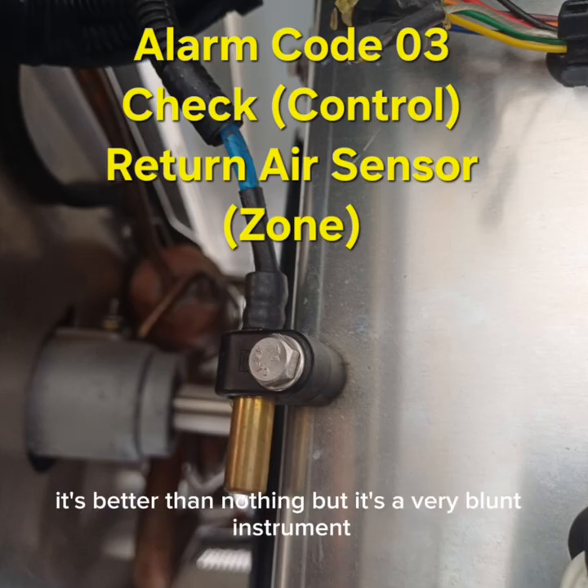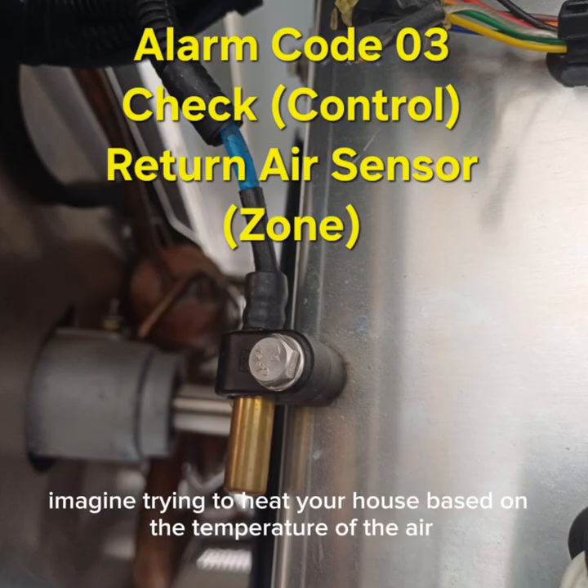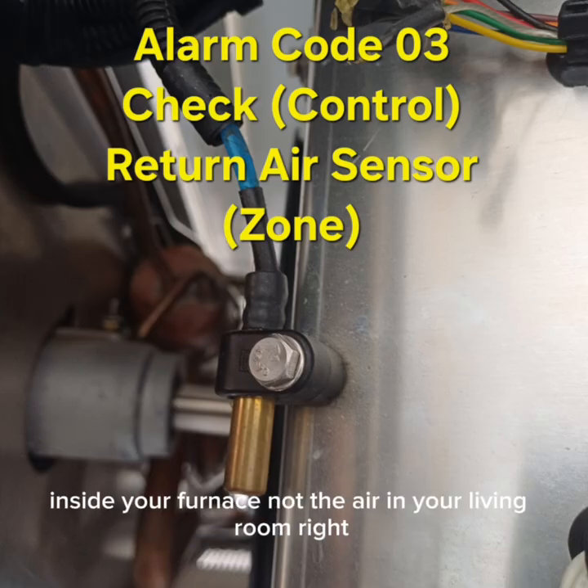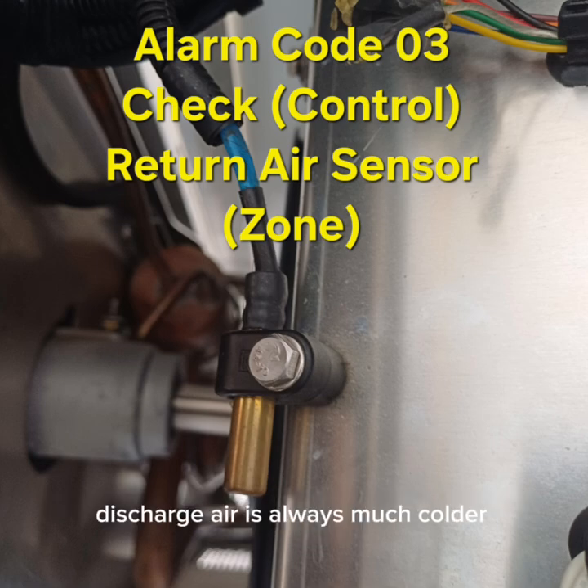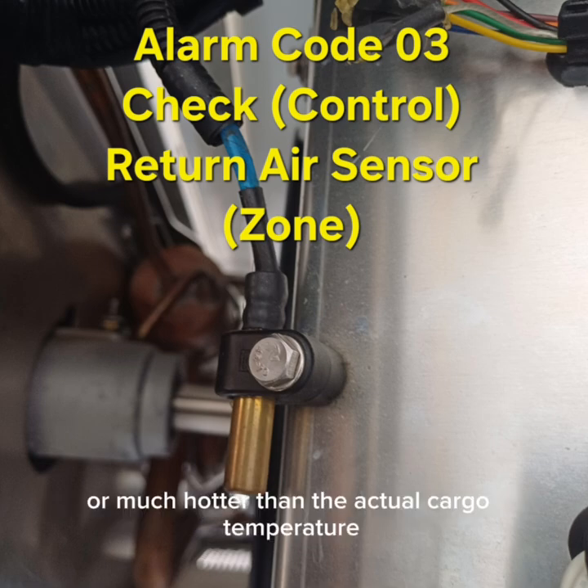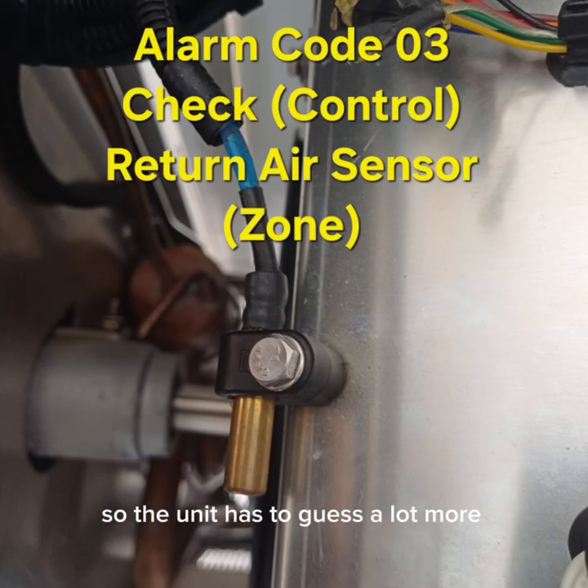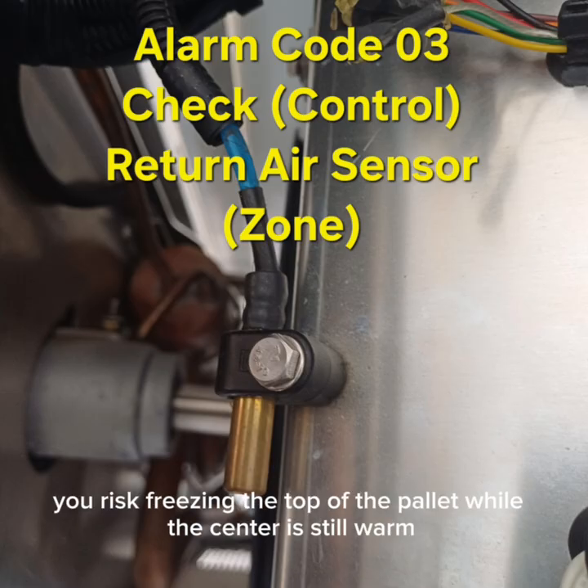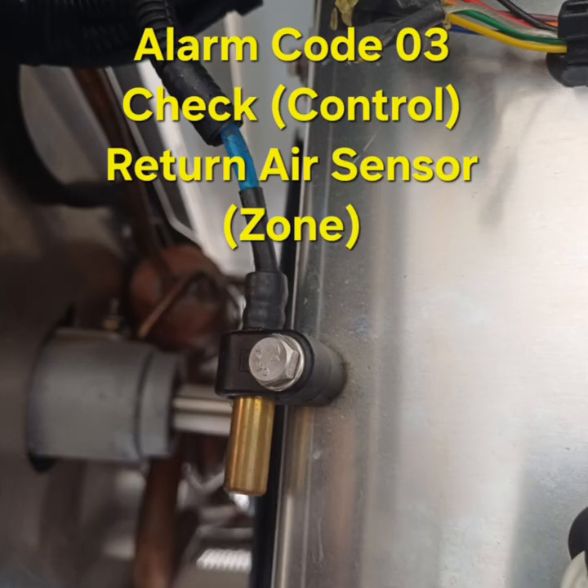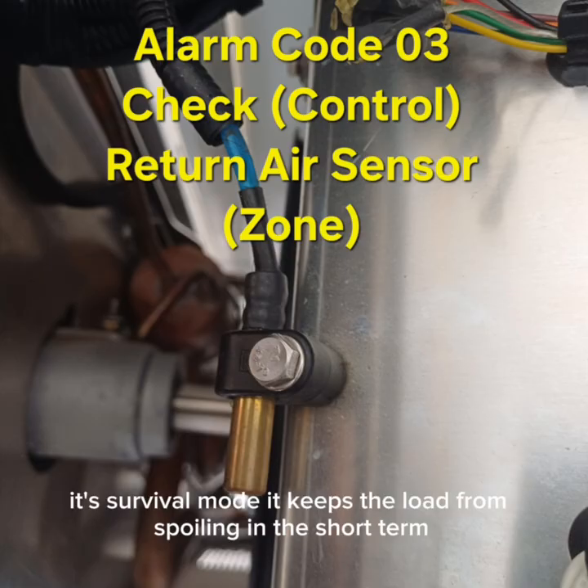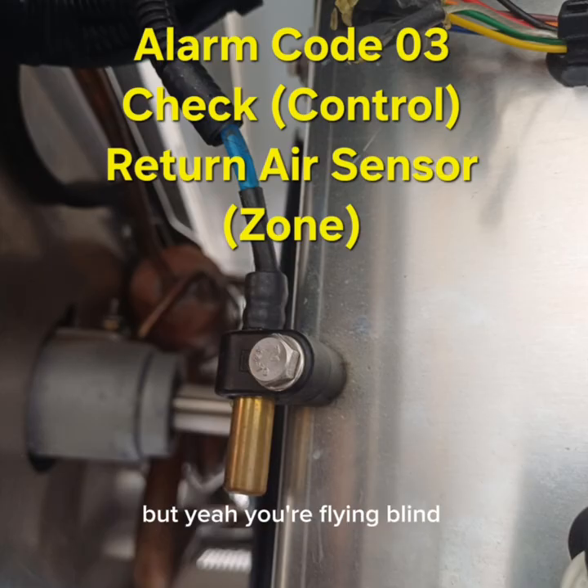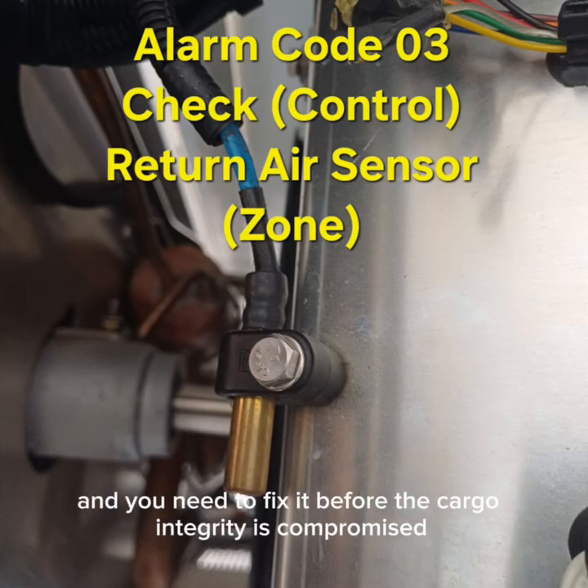It's better than nothing, but it's a very blunt instrument. Imagine trying to heat your house based on the temperature of the air inside your furnace, not the air in your living room. Right. Discharge air is always much colder or much hotter than the actual cargo temperature, so the unit has to guess a lot more. You risk freezing the top of the pallet while the center is still warm. So it's basically limp mode. It's survival mode. It keeps the load from spoiling in the short term, but yeah, you're flying blind. You still have that flashing light, and you need to fix it before the cargo integrity is compromised.